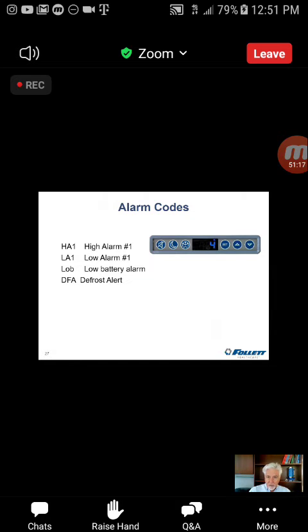DFA, defrost alert. We're going to get into the specifics of the defrost cycle when we get to the electrical section, which is coming up very shortly. The defrost will terminate either on time or temperature. We want it to terminate on temperature. That means that as soon as that evaporator gets to 41 degrees Fahrenheit, 5 degrees C, as we heard when we were looking at the defrost components, we want to terminate right then and there, because the longer we stay in defrost, the longer we can't provide cooling to the product.